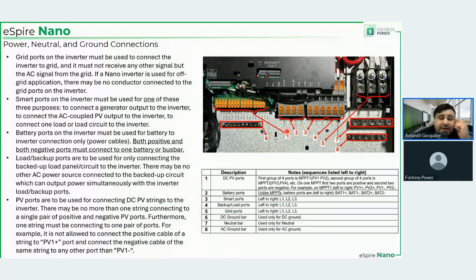You can use thinner cables. It's easier to manage. And also, to be able to extract maximum charge and discharge power, you must have 2 positives and 2 negatives connected, right? Because each of them separately is not rated at 100 amps as we rate 2 positives and 2 negatives together. 2 at the same time, yes, they can carry 100 amps, but each separately can only do, I believe, 83, if I'm not mistaken. So 2 positives and 2 negatives is kind of cool.